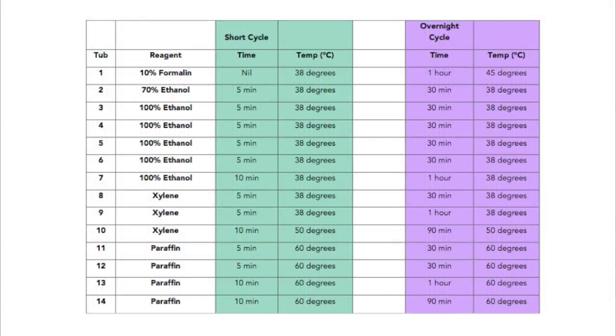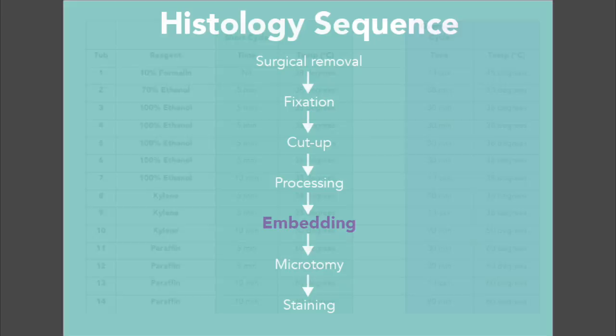Typical processing cycles might look like this. Notice how the cycle times are much longer for the overnight cycle. Processing times can be reduced by heat, agitation, low viscosity of fluids, and decreased pressure. Once processing takes place, the tissue is moved to the next step: embedding.